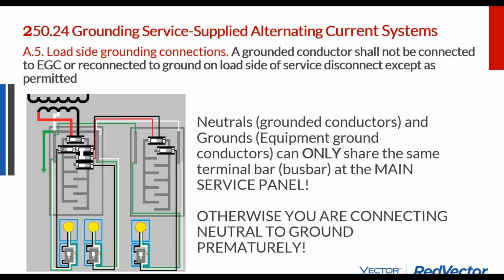If that return through the neutral doesn't make it all the way back to the service panel, our ground fault detection circuits can't work. They can't monitor where that electricity went. And so particularly with those faults that are less than the main breaker rating, if we can't monitor and track that, then those ground fault detection circuits don't work. And so the only way that ground fault detection circuits work is if there's only one location on a service panel where the neutral's connected to ground.